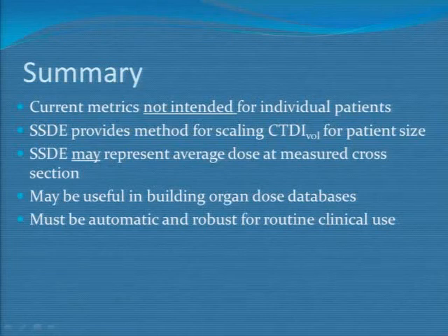Mike, let me give just a perspective on that. The internet is replete with information that consumers look at. We had this case that Diana mentioned, where the SSDE was used. Actually, the technologist gave the parent the CTDI and DLP for a pre- and post-surgical exam. Unfortunately, the patient had a CTDI estimate on a scanner that used the 32-centimeter diameter CTDI phantom, and after the fact, on a 16-centimeter diameter phantom. Now, just guess what happened.